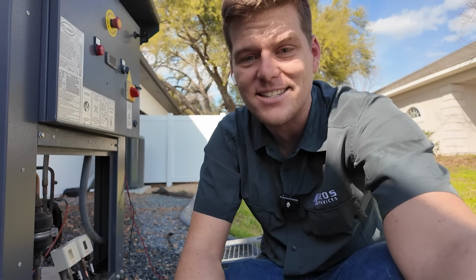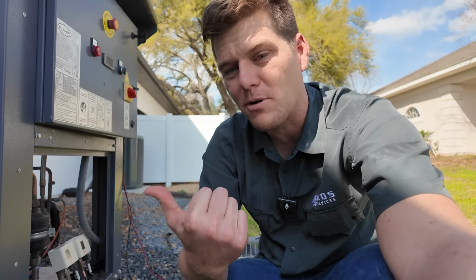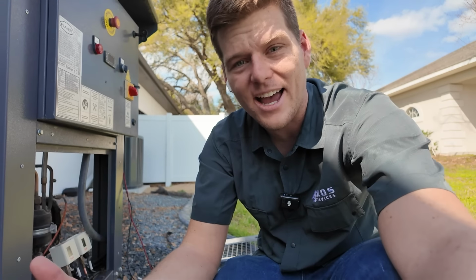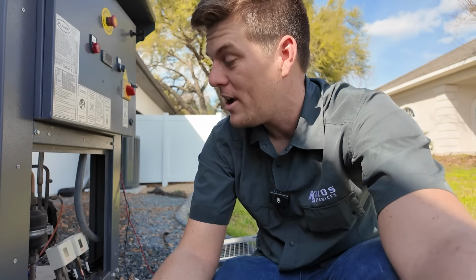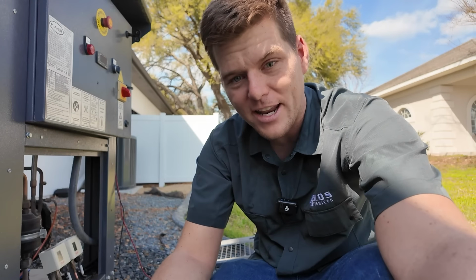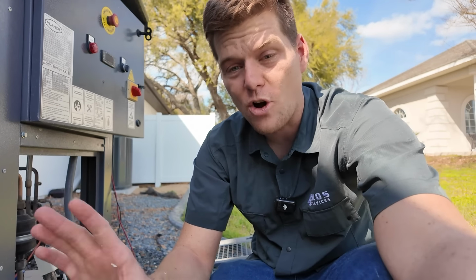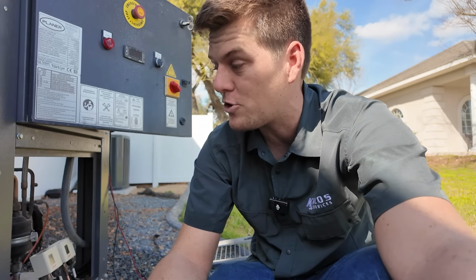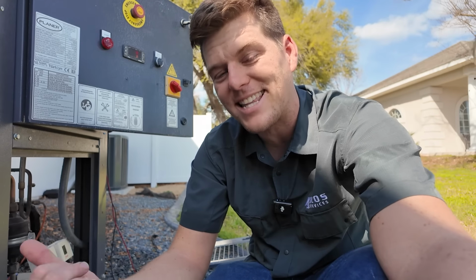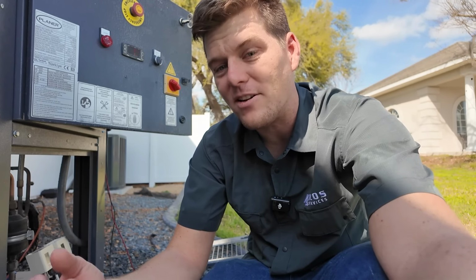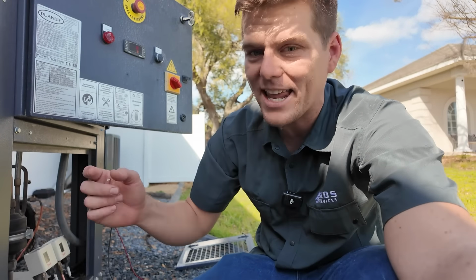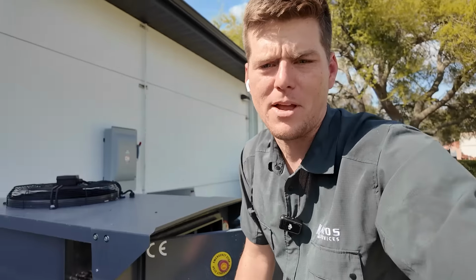Now, remember, this is a cascade system. So this system isn't responsible for actually doing the work inside. No, it's responsible for removing the heat that's created from the compression process inside. There's a whole separate system inside that's responsible for doing all of that. This just needs to make sure that it gets the heat out of the water from inside and then transfers it to the refrigerant, which then blows it off in the top of the system up top.